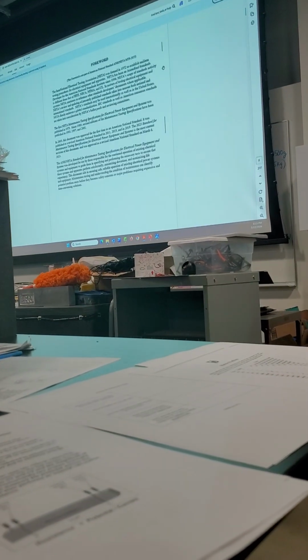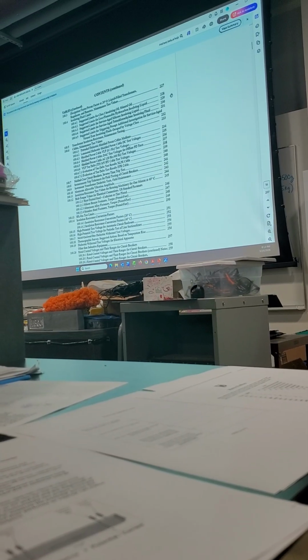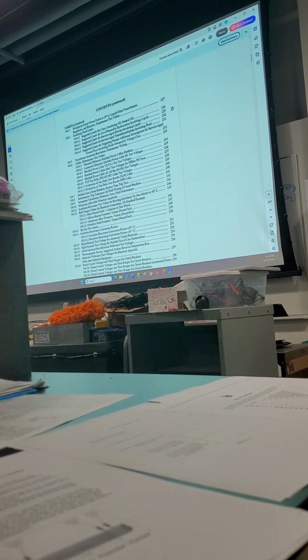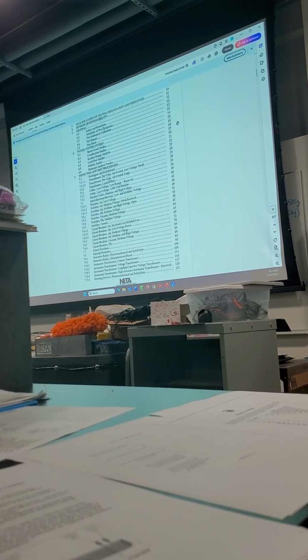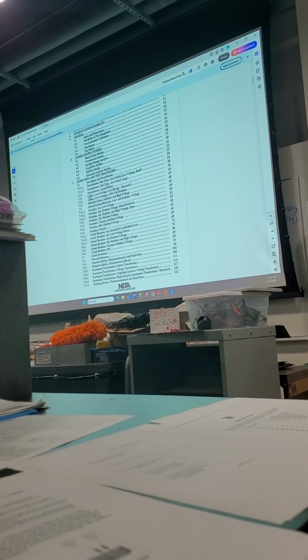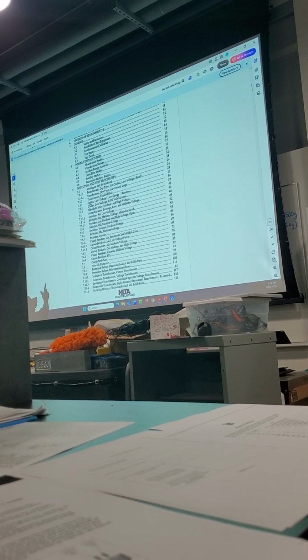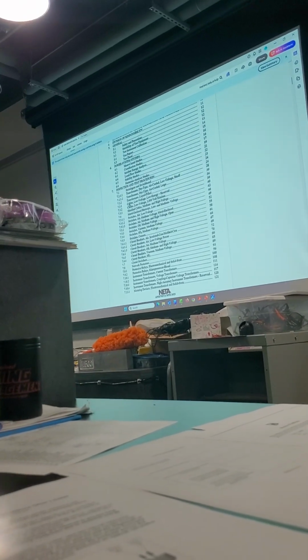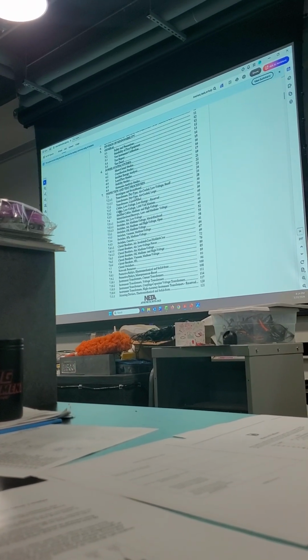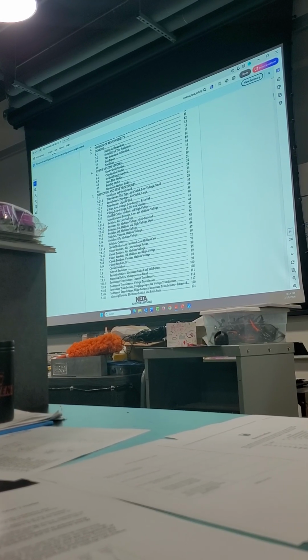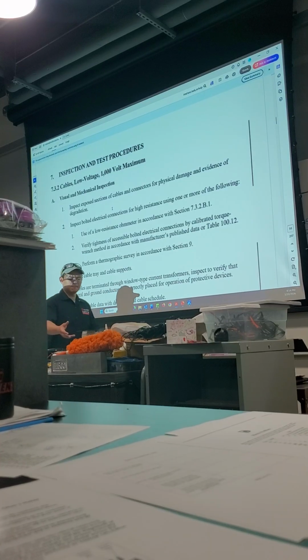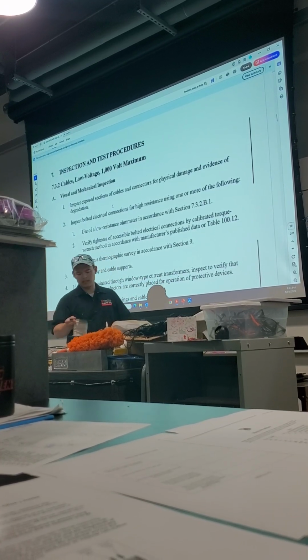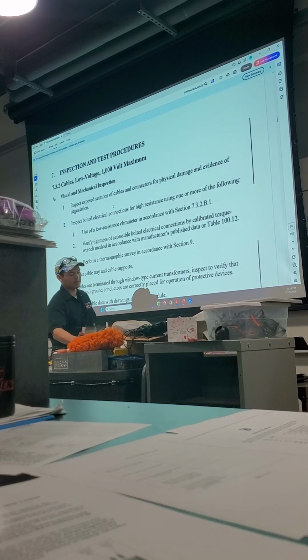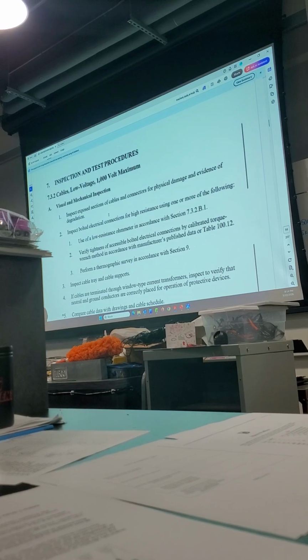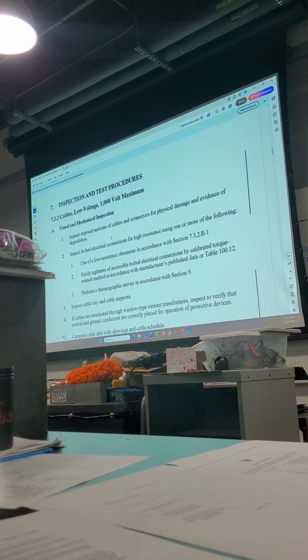So take your NETA MTS book and we're going to take a look at the relevant sections here. Always start at the table of contents, just like our NEC course. So, because we are looking at tables, we'll walk before we run. Let's take a look at our tables, low voltage, low energy. That was a reserved section, so that's actually in progress. But let's go to page 40, or whatever version you may be running. Cables, low voltage, 1000 volt maximum. Which actually may be along these lines. Of course, they don't normally run at 1000, maybe they'll be a 120, 208 kind of thing. But they're actually rated for usually up to 600 volts. So 1000 volt max, let's start with here.